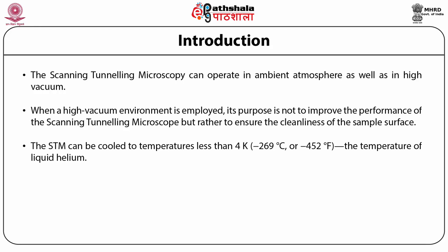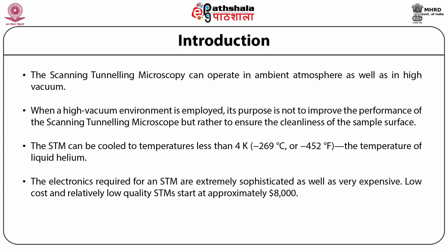The STM can be cooled to temperatures less than 4 Kelvin (minus 269 degrees Celsius or minus 452 degrees Fahrenheit), the temperature of liquid helium. It can be heated above 973 Kelvin (700 degrees Celsius or 1300 degrees Fahrenheit). The low temperature is used to investigate the properties of superconducting materials, while the high temperature is employed to study the rapid diffusion of atoms across the surface of metals and their corrosion properties.